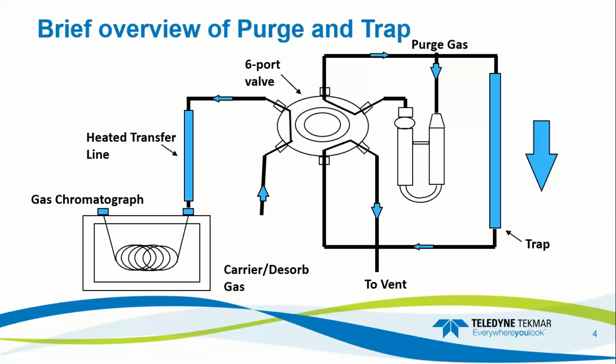and flow. This flow is controlled by a mass flow controller or a pressure regulator that monitors and precisely controls the gas flow rates throughout the entire purge and trap process. From there, the six-port valve directs the gas containing the analytes to the analytical trap for concentration.